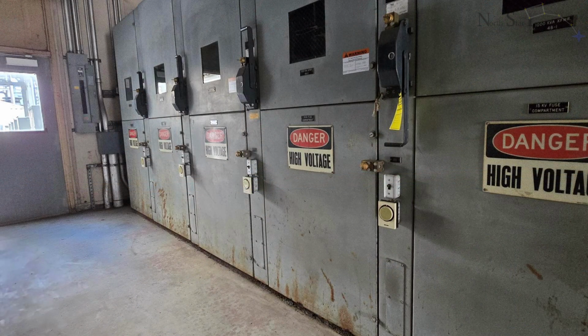There are also many environments where dust and debris make their way into substations. This can be anything from typical factory production dust to new construction kicking up dirt. If the outside of the substation is dirty, there is a good chance that the inside is too.